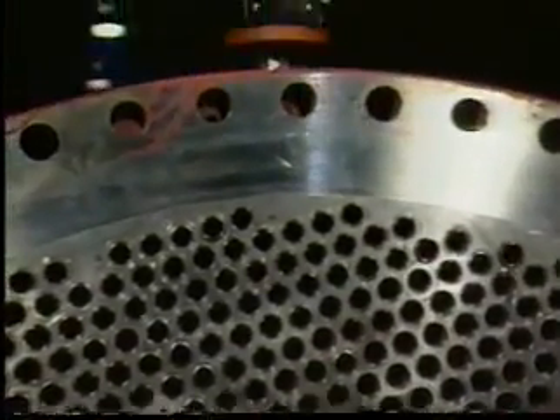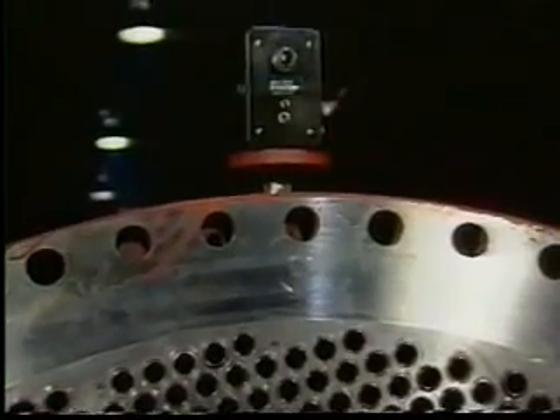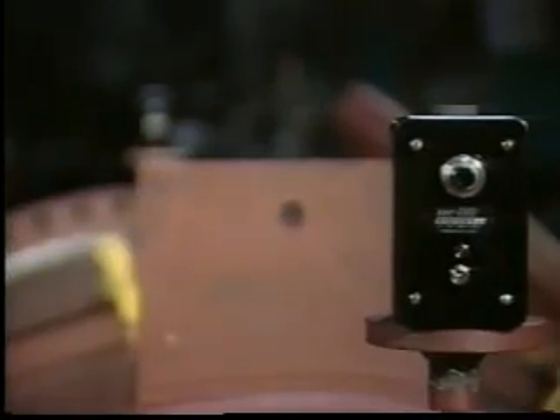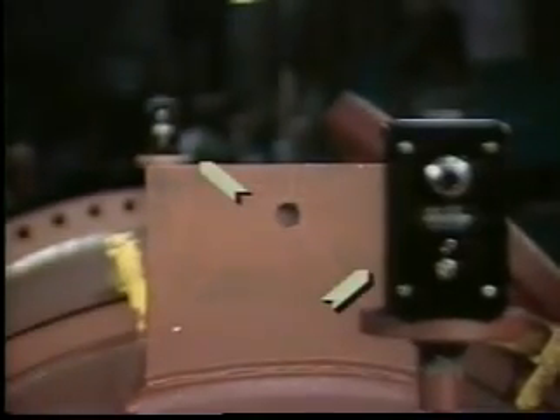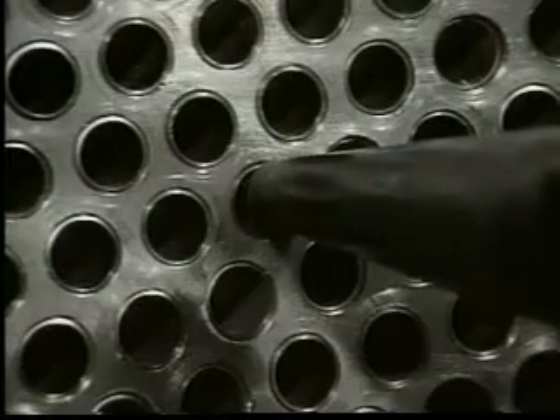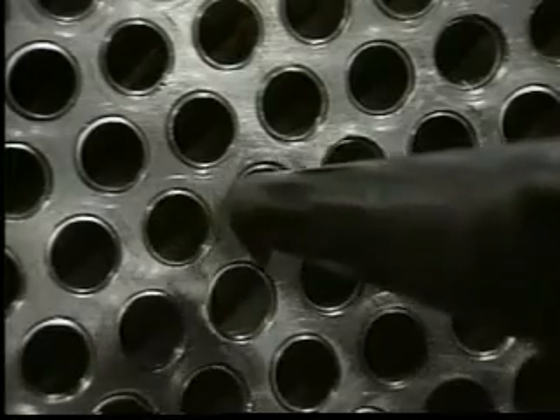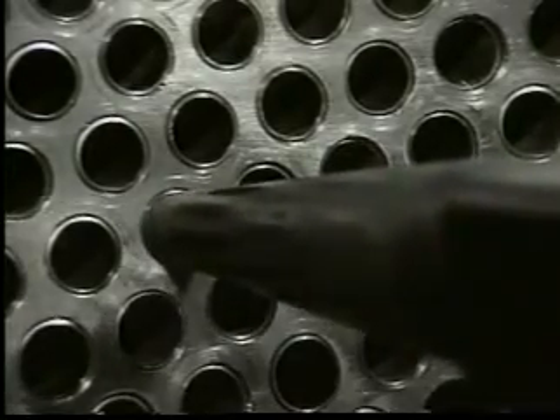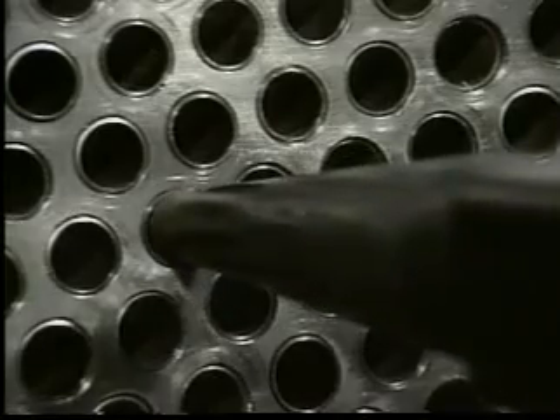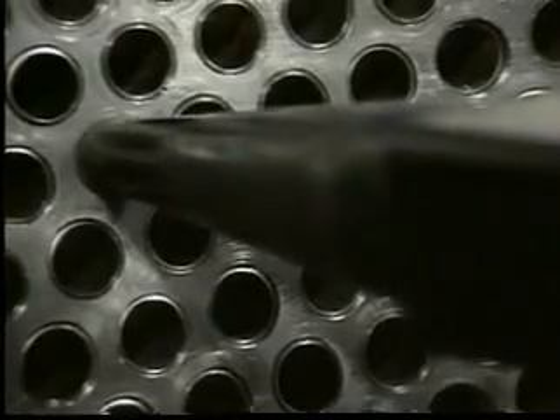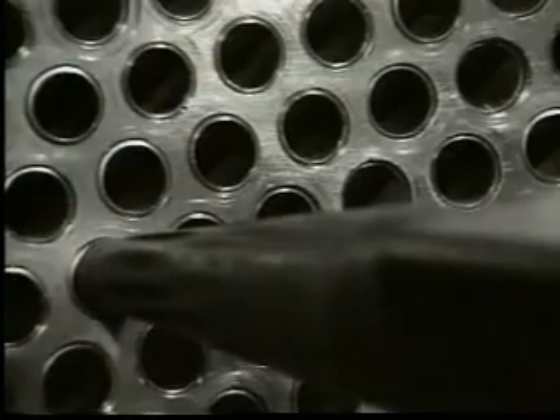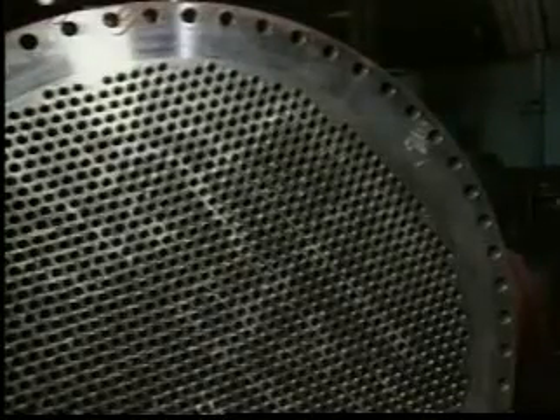UE Systems WTG2SP warble pipe tone generators are used. Use as many tone generators as may be necessary in order to achieve as uniform an ultrasound field as possible around the tube bundle. As an example, place one in the inlet port and one in the outlet port. Proceed as with the other leak detection methods, scanning for the sonic penetration of the warbling tone. In some exchangers, if sound does not travel to the far end, both ends should be tested.